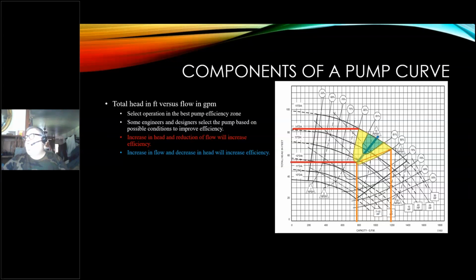So some designers will pick the operating point between these lines, okay? And that's where they think they can operate in whatever conditions in the field. This also comes into play sometimes with our variable speeds, where we want to change the amount of flow we have. So if you really think of it this way, you can get up to 1200 or down to 780, as long as your resistance isn't above or below the red lines. Okay. That picks these curves, these three we can operate with in those zones. So it kind of narrows down where we can apply this pump.